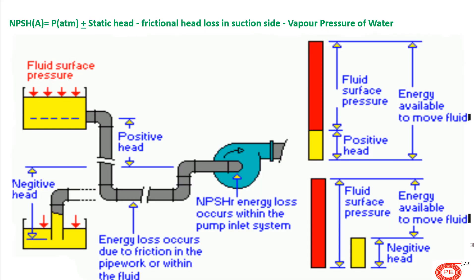Now let's see with the help of a sketch how to calculate the values. The complicated formula from the last slide is simplified here. P_atmosphere corresponds to HA; the static head corresponds to HS (plus or minus); HF is the frictional loss (minus). HV is a very small value that designers neglect and don't consider while calculating NPSH. The last term is HVP — the vapor pressure of the liquid.